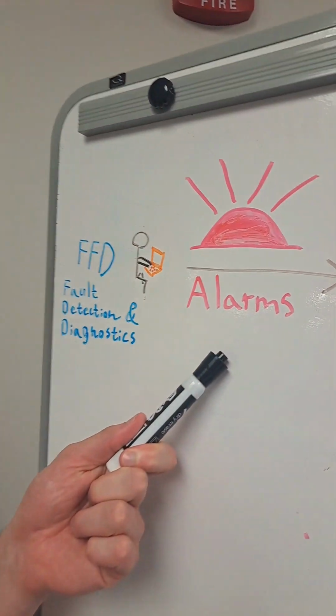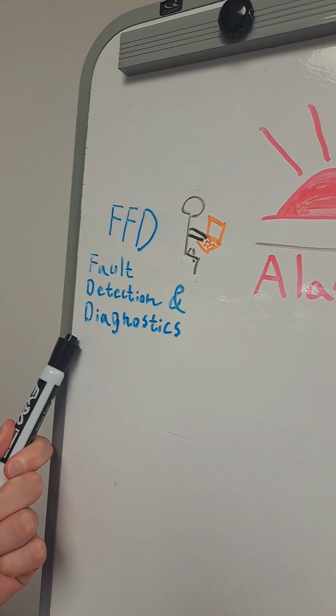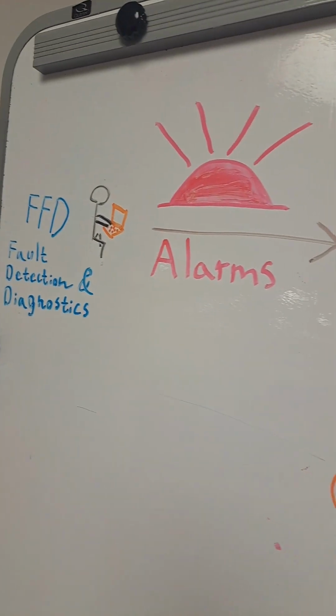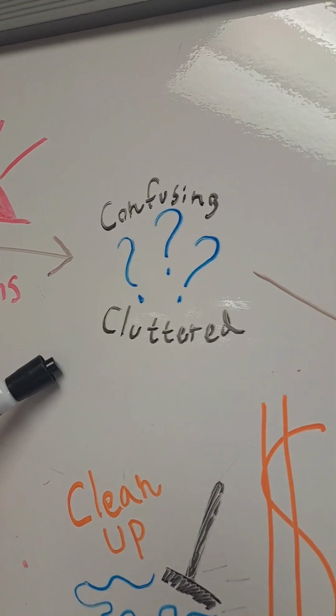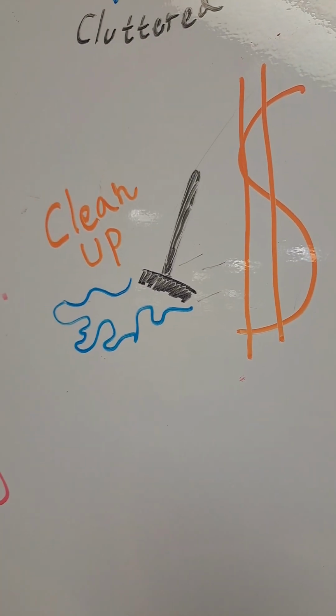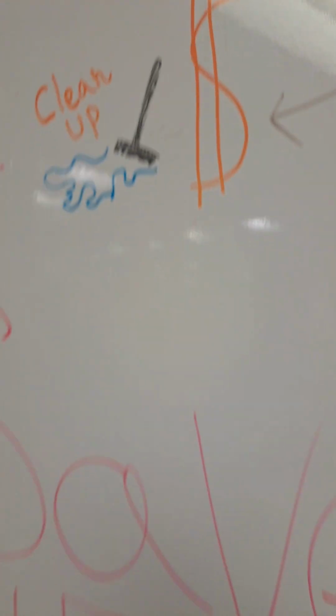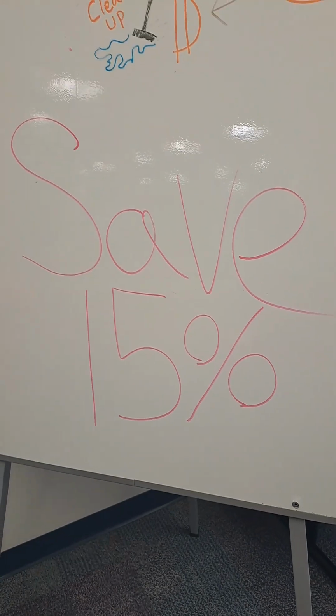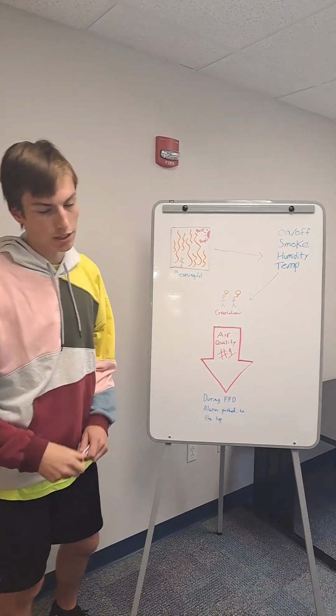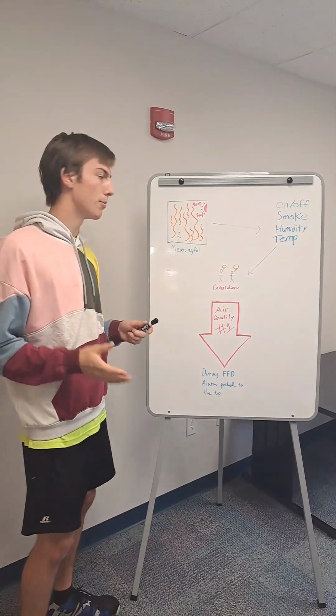One of the main purposes of building automation is to save energy and money. But what happens when an alarm goes off? This is when proper fault detection and diagnostics comes in handy. Without this, alarms become confusing and cluttered, which leads to wasted time and money. If proper fault detection and diagnostics is used, a building can save up to 15% of its energy consumption. How does proper fault detection and diagnostics actually help a building save money?